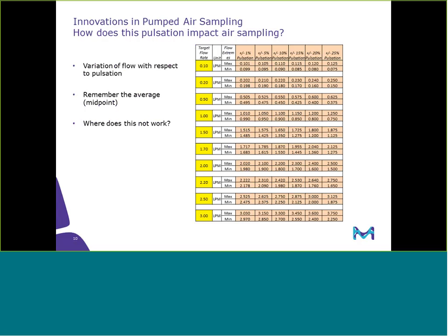So here's a chart showing, I know it's a little busy, the relationship of the effect of percent pulsation on flow rate. This is based on an ideal wave pulsation. As you can see, the maximum and minimum flow rates are shown in the beige fields, hopefully that's beige for everyone, it is for me, for your set flow rate shown in the yellow fields. And they could be quite different as the pulsation value increases. Observing these pulsations would not be evident with the use of some calibration devices, so you would have no idea that these pulsations really truly exist.